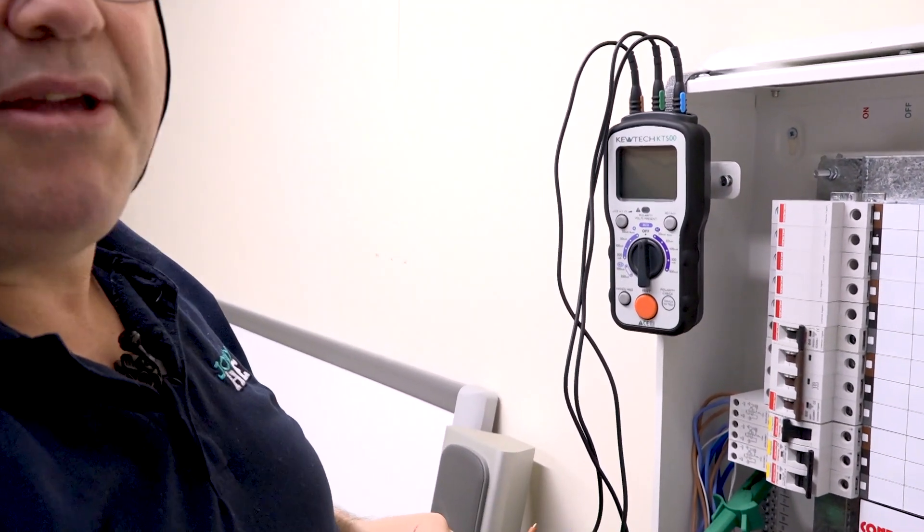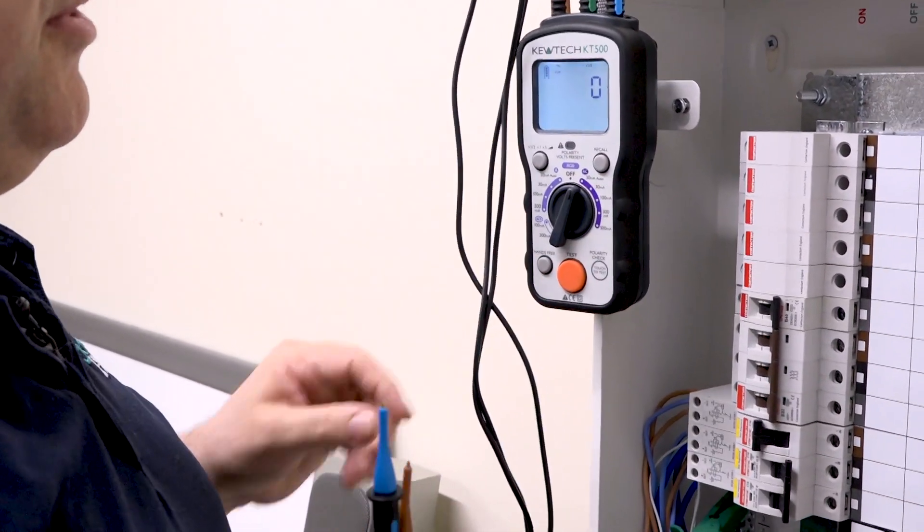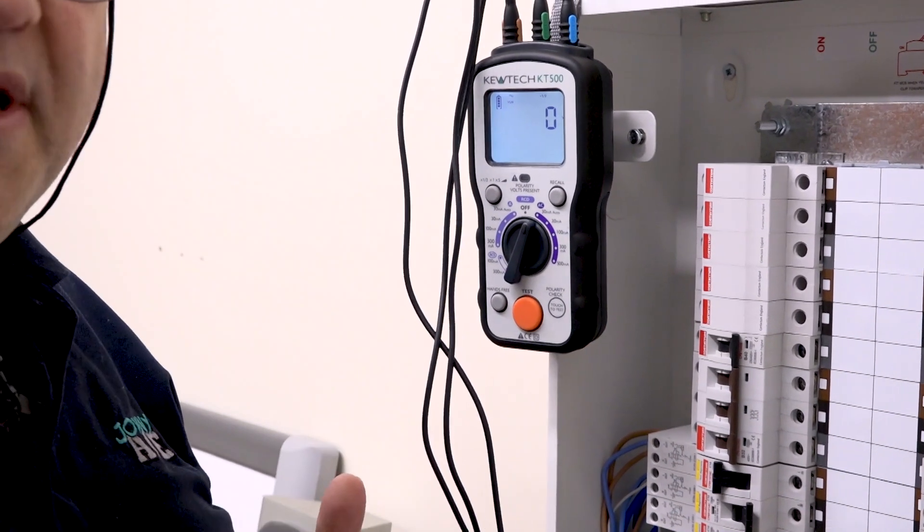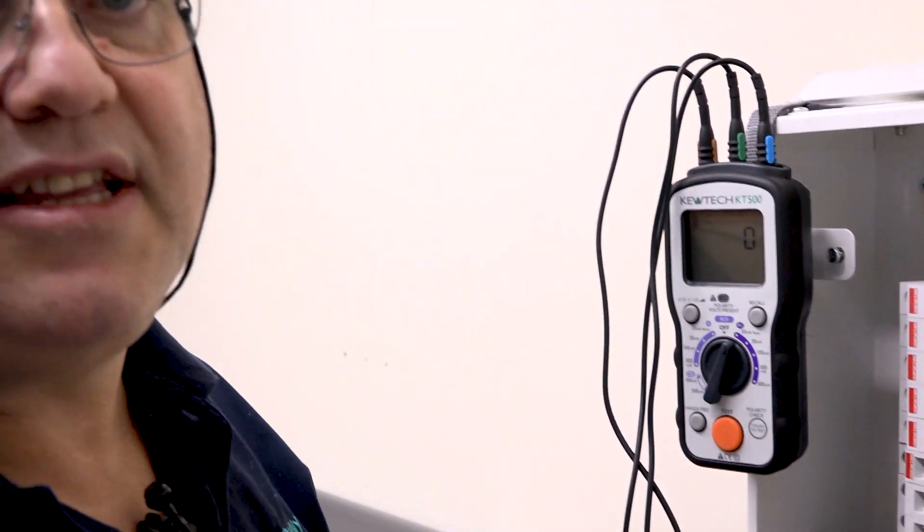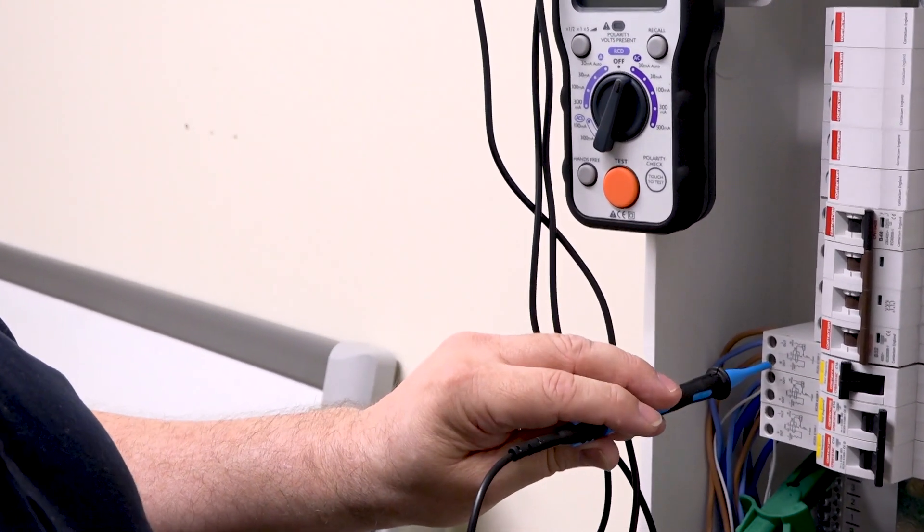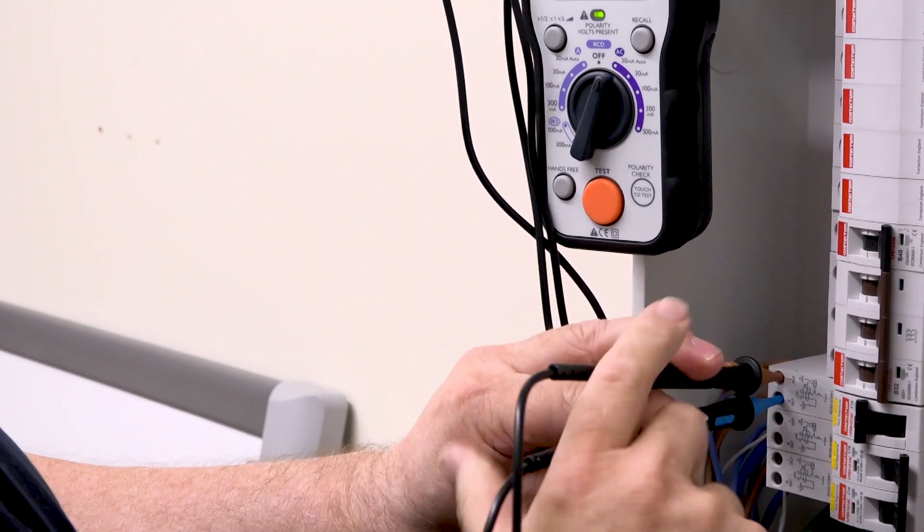As you can see, we've got the earth connection on the DB already. So I'll turn the tester on, put it into AC on the 30 milliamp. Also, all the loads have been disconnected so there's nothing connected into the circuit. The CPC is onto the earth, we'll put the blue probe onto our neutral, brown onto the line.